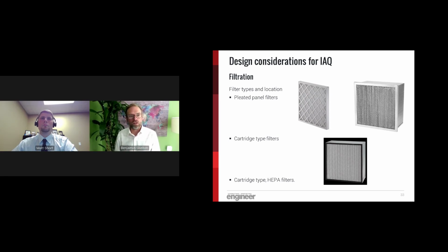We have to look at each application to see if the cartridge filter, or the bag filter, or the pleated filter is going to be applicable. From an energy standpoint, we want to try to maximize the efficiency of the filtration for the building, but we also want to try to minimize the energy consumption. These filters stay in place; they're a constant draw on energy.